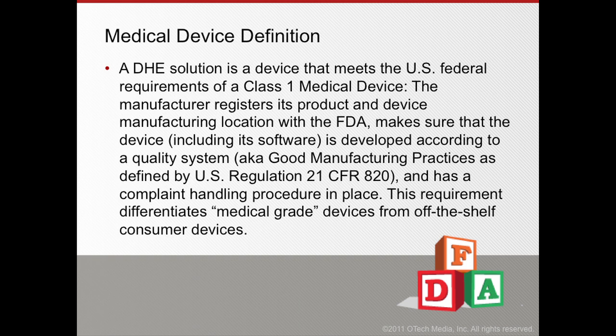Another important component is that medical devices, including their software, are developed according to a quality system — meaning good manufacturing practices. That means the software is controlled, there is a list of what releases were implemented, there is a complaint handling system, and you can track back errors and problems and issues. Good manufacturing practices are critical to make sure that the product, the device, the software has a certain level of reliability. This requirement really differentiates medical devices from off-the-shelf consumer devices.